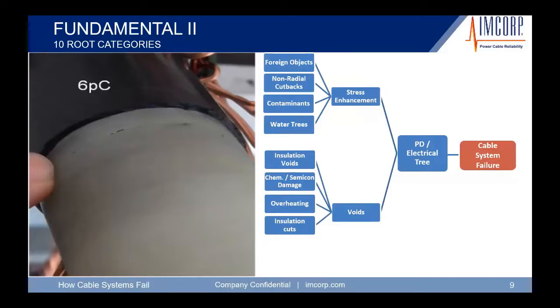We weren't able to find the issue initially. What we did is we made another ring cut, took this thing back, and we were able to find the cut in the insulation. Really nice thing about using EPR, we showed the guys how they can bend the EPR, and there's a discoloration, it whitens up a little bit to show any cuts in the insulation. On something like this, you'd have to do a cutback or make an additional cutback, sand that out to make sure you got the cut out of the system, where you could have partial discharge.